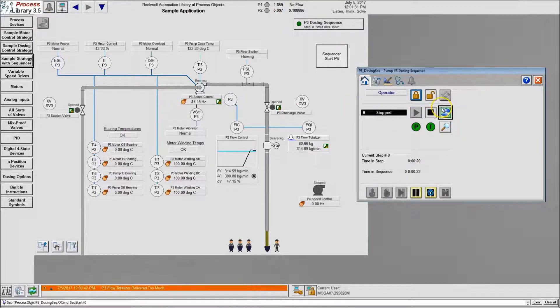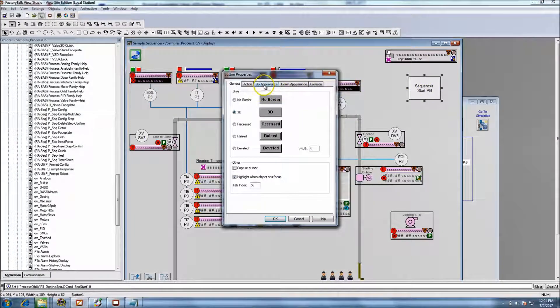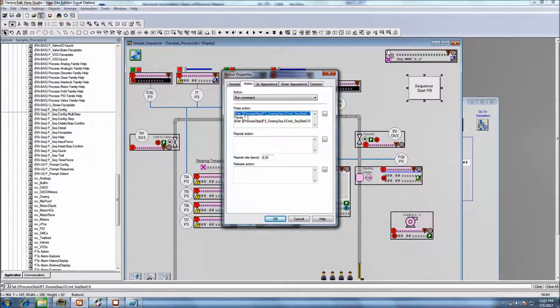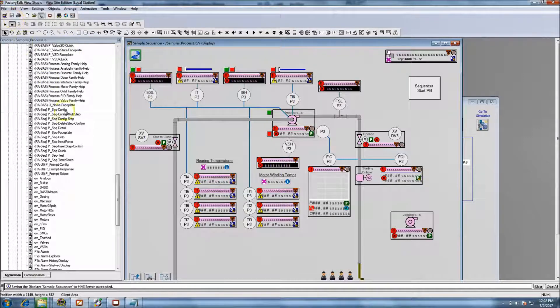The main focus I wanted to show is the use of setting the bit to one - you press it, you set the bit to one, you pause, then you come back and set the bit to zero. The reason you're doing that is so that if there was a lag or any kind of communications problem, or what we'd call a sticky button HMI situation - if you had some Windows graphics problem - you could still get by. You pause for two seconds, then set it to zero.